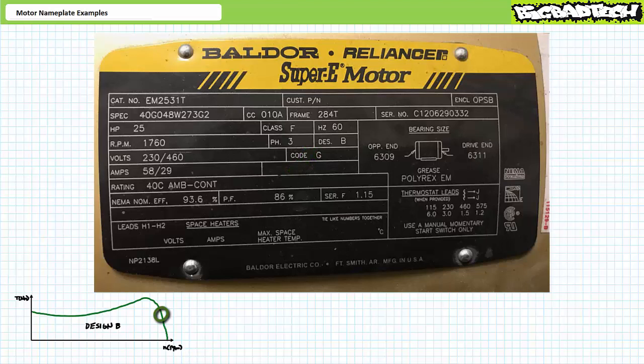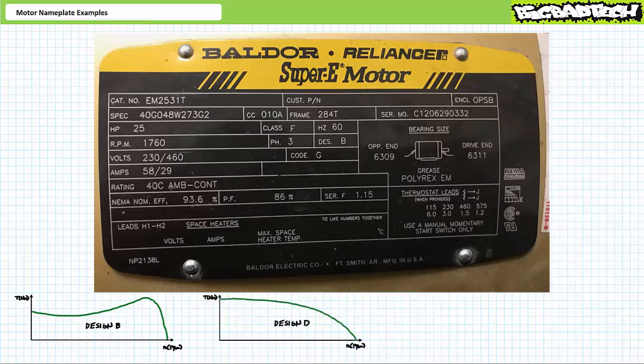At the rated condition, the motor turns at rated speed and produces its rated torque. At less than the rated condition the motor will speed up; at more than the rated condition the motor will slow down. Anything to the right of the rated condition is an underload; anything to the left is an overload and isn't meant to be sustained. NEMA Design B motors are general purpose induction motors, whereas NEMA Design D motors are for high torque, low speed applications.